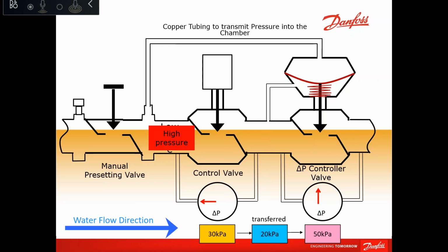Usually the installer de-airs the system, because air inside the PICV does not affect the PICV so much as it affects the system and the pump. The small air bubbles will become like a big cavitation when reaching the pump section, and this will destroy the impeller. But if there is air in the PICV, you can purge it out by pushing the spindle of the PICV up and down multiple times, then you can purge any air bubbles inside the valve.